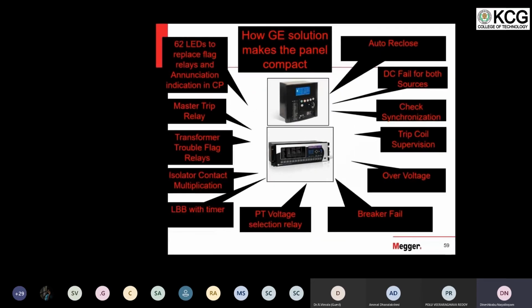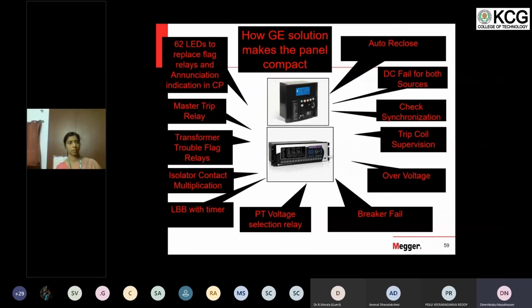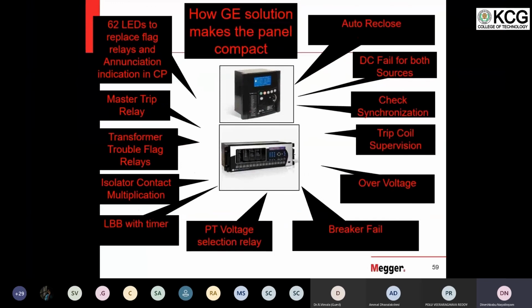Of course, you cannot compare the life of a numerical relay with the electromechanical relay. Electromechanical relay can work for 50 years or plus. Even now, when we move to some substations, we find some relays installed before independence. Still, they are working perfectly. However, we are running another numerical system in parallel because they can only trip. They cannot give additional information.